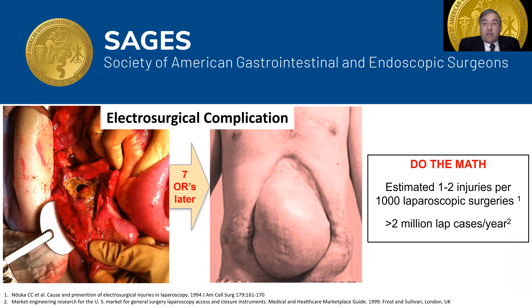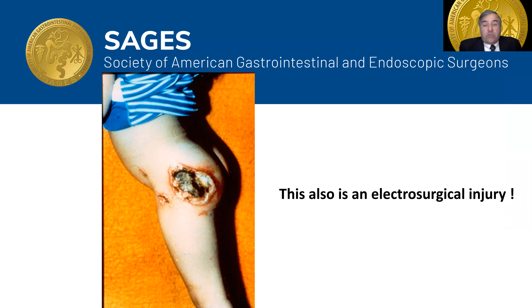Here's another devastating injury. I'll give you 5 seconds to guess for yourself what happened. The burn is from an electrode, a return electrode. We don't call it a grounding pad, although many still do. Nothing is being grounded in electrosurgery anymore. It's part of the electrical circuit. Therefore, this is charged with energy, and it's delivered through the electrode and can lead to deep burns if the electrode or the returning pad is not placed correctly. In a poll done at SAGES, 1 in 10 surgeons thought that it is okay to cut a return electrode to size. That's the outcome you get doing that.